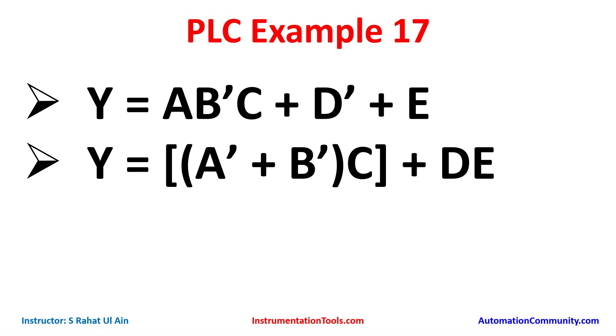We will start with the first expression. For inputs A, B, C, D, and E, we'll use normally open and normally closed contacts. B and D will use normally closed contacts, and A, C, and E will use normally open contacts. A, B, C will be connected in series, then D' in parallel, and E in parallel — giving us AND logic followed by two OR logic gates.